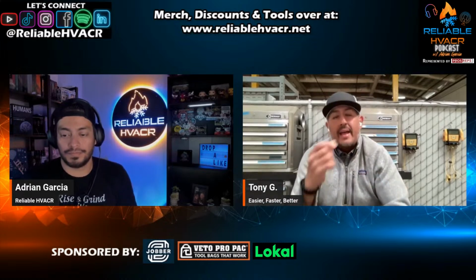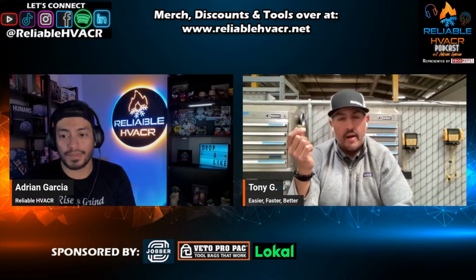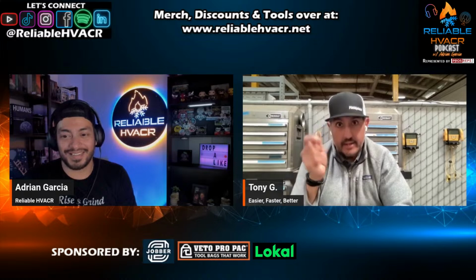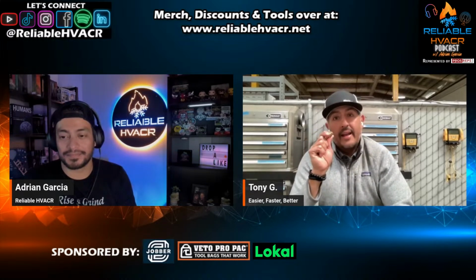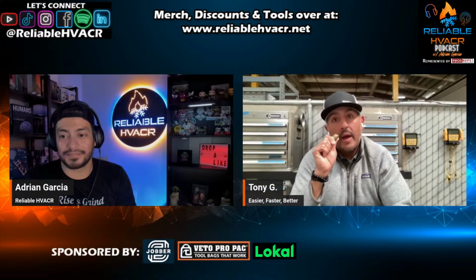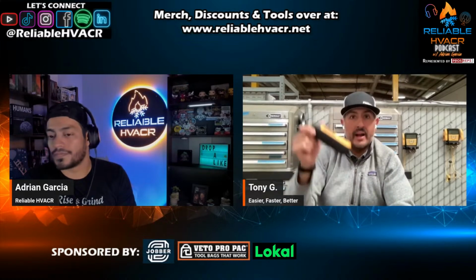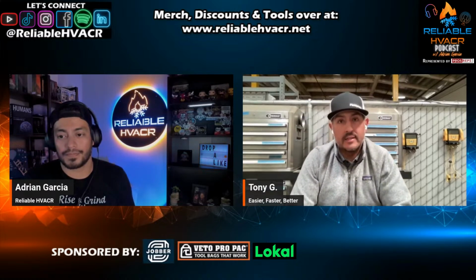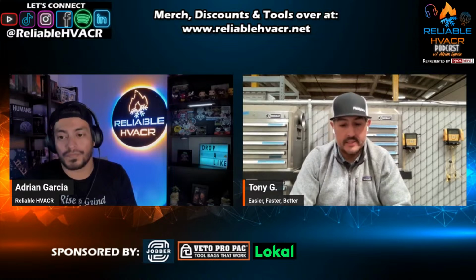Sometimes we have a micron gauge connected in line in our line set. A lot of people ask me, but Tony, don't your S-Man manifolds have a micron sensor in there to measure microns? Yes, they do. And what I would say to that is that is an okay way to measure microns, but the best way is to have a dedicated micron gauge and connect it straight to the system, either on one of the service ports or on an entry point into the system.